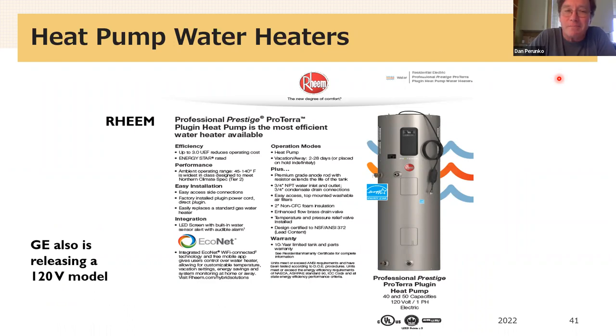This is a new thing that I don't know what to think about. There's some research about these that I just heard about. I haven't had a chance to read yet. This is a 110 volt heat pump water heater. All the other ones that I showed you were 220 volts. And so this machine has less access to electrical power than the other machines do. And as a result, it can make less hot water in any given time window than the other machines. And what's exciting about these is a homeowner could install this themselves, or a contractor who didn't have the ability to work on the electrical system could install this, because it just plugs into a wall plug, right? And it has a built-in circuit breaker in its cord. So if it's drawing too much power or there's a short or something, it should trip itself off. So it has some added safety.